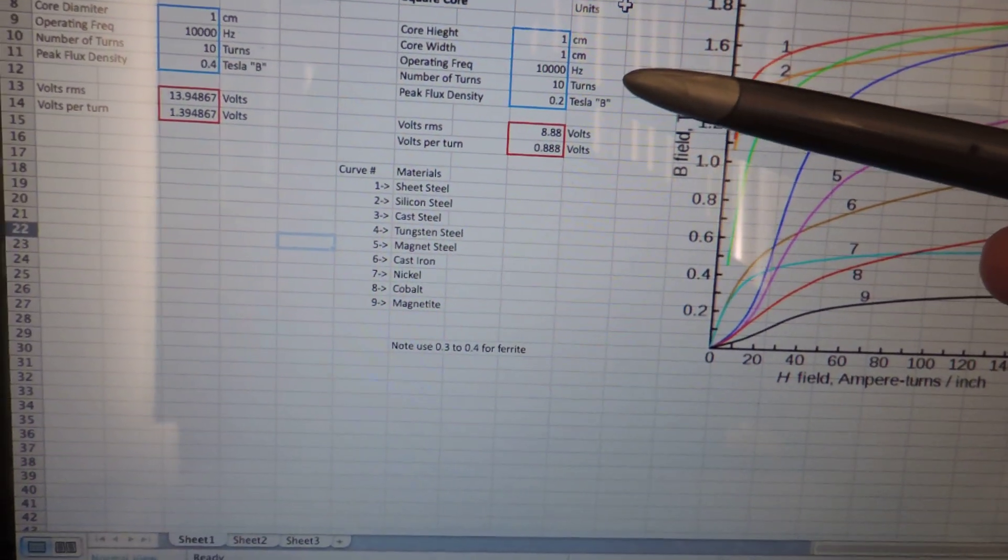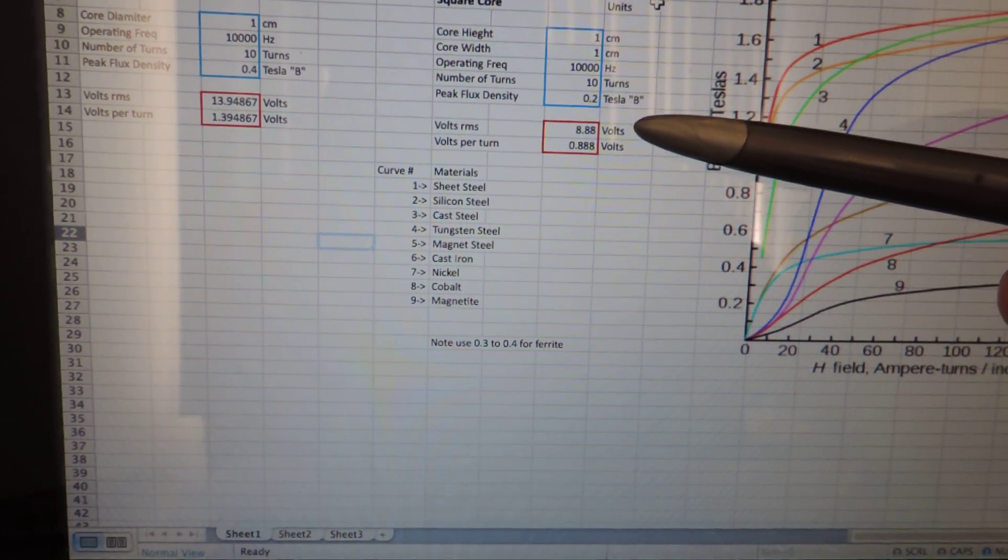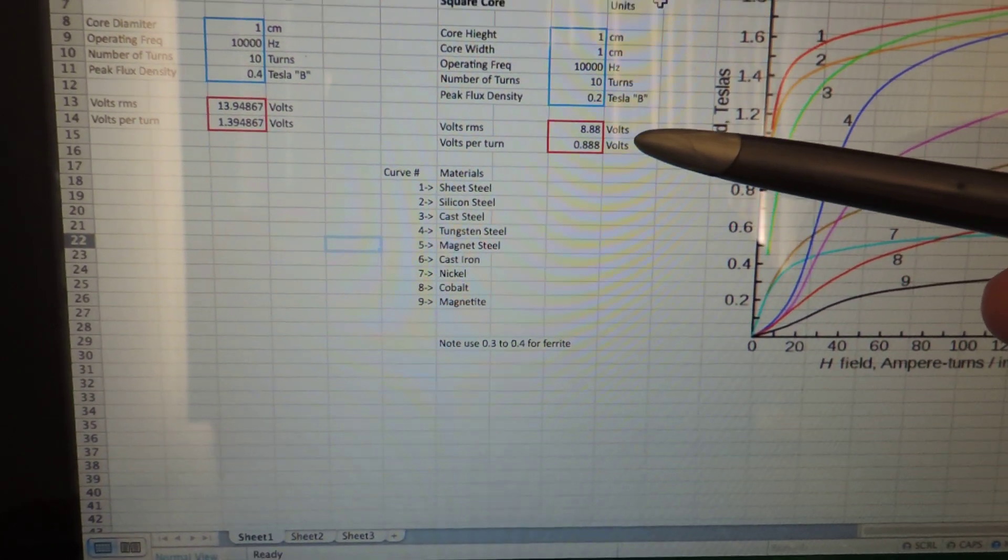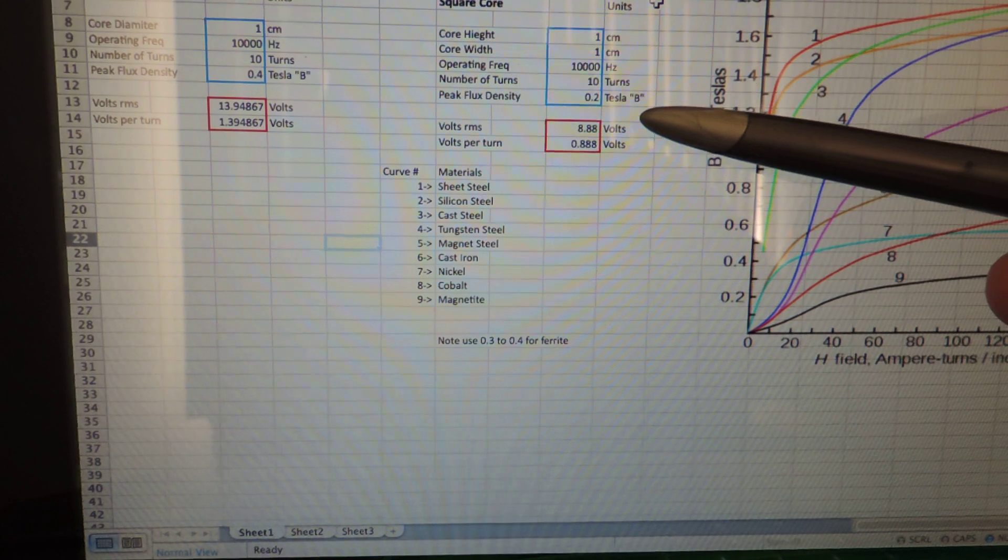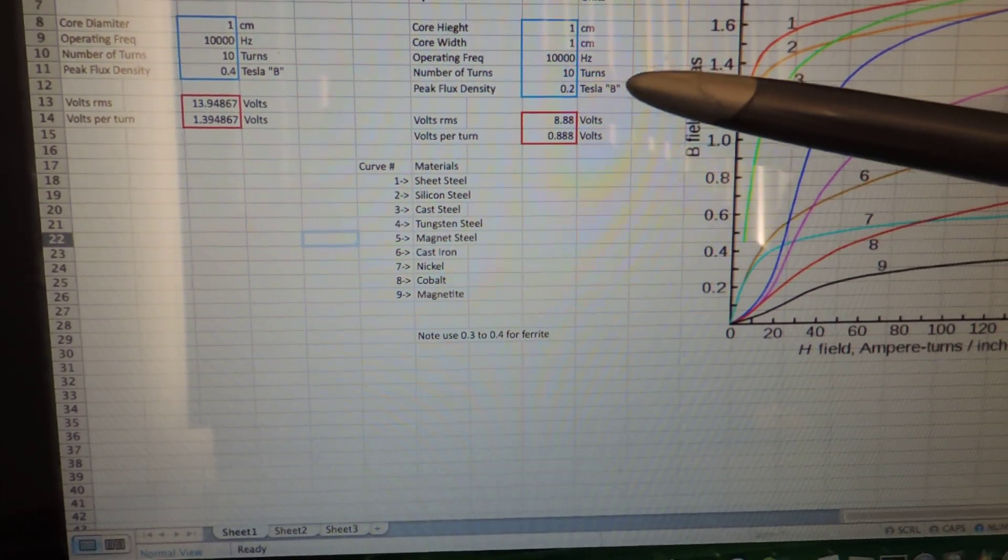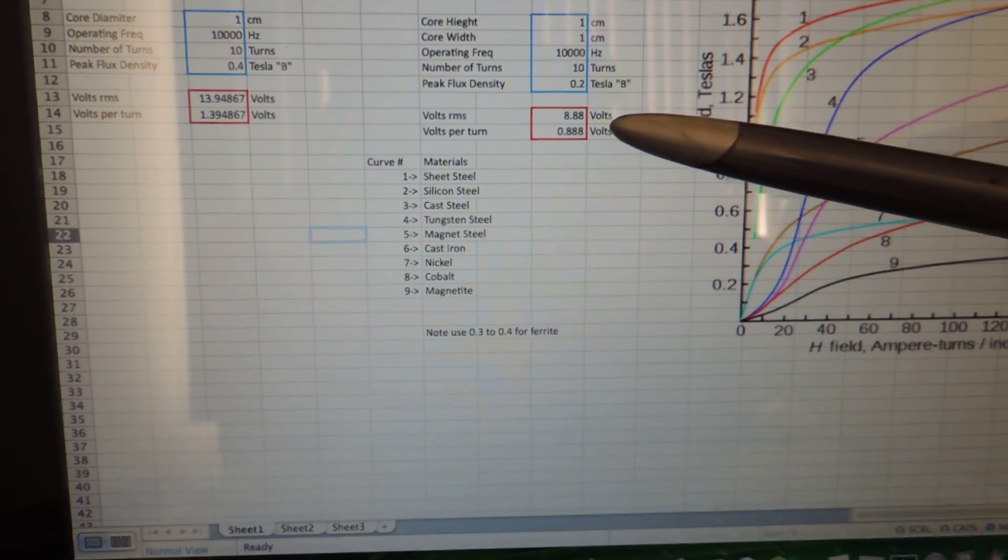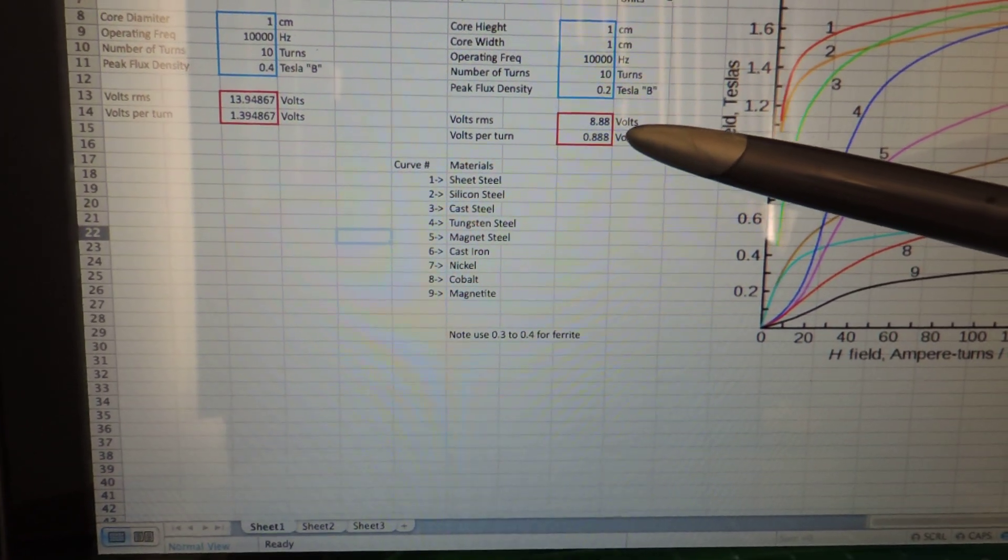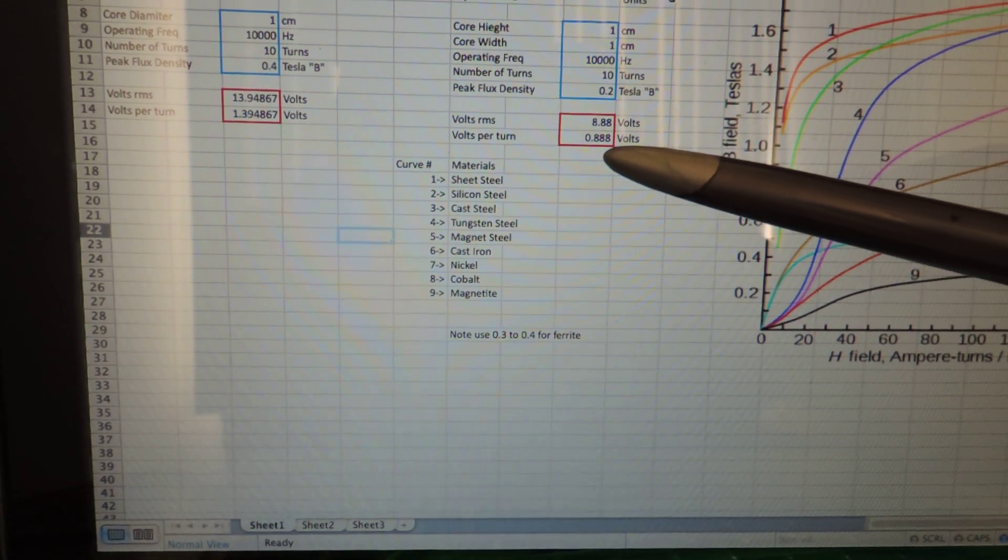In this particular example, we're using 0.2 tesla. And you can see here, it gives us a voltage RMS of 8.8 volts. This is the maximum amount of voltage we can apply to 10 turns on that type of core, before it saturates it. And you can see here, you can divide that number by the number of turns, and you can get voltage per turn as well. In that case, it's 0.88 volts.